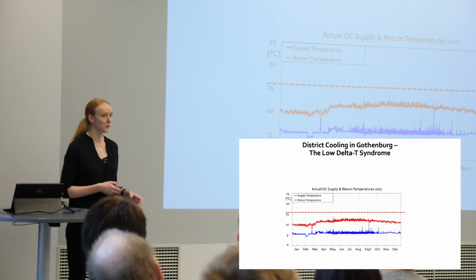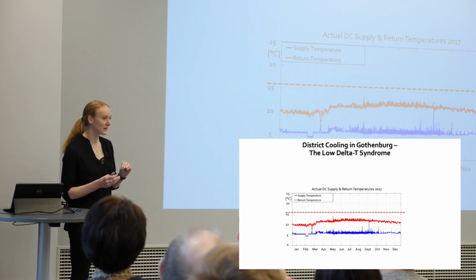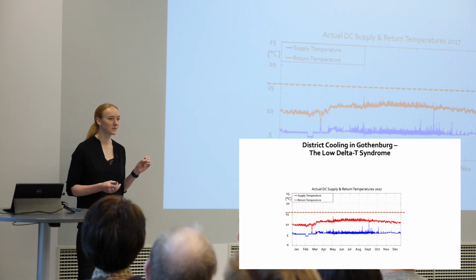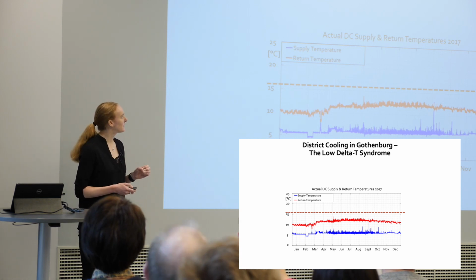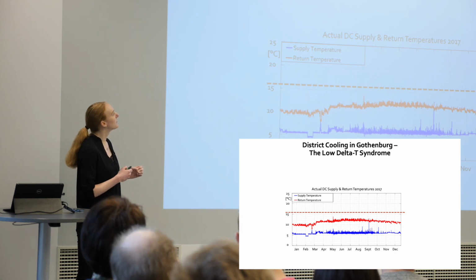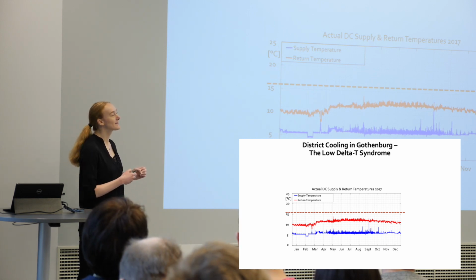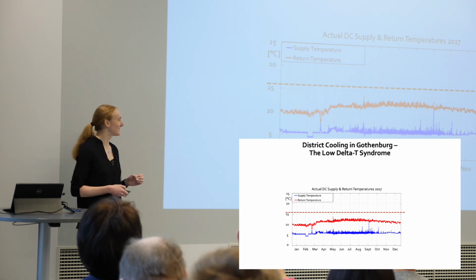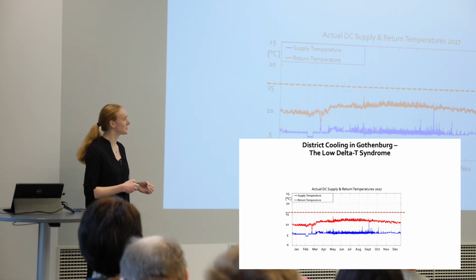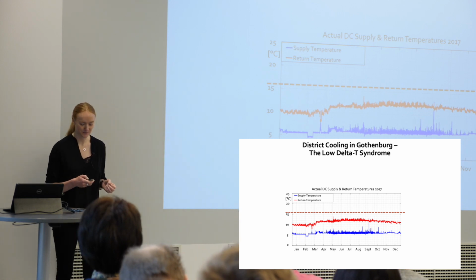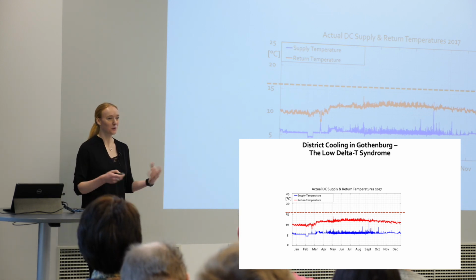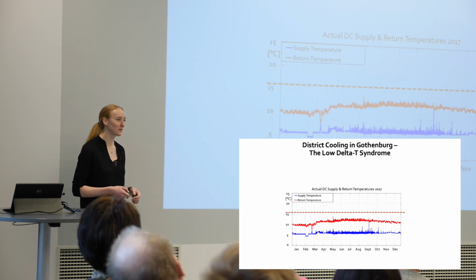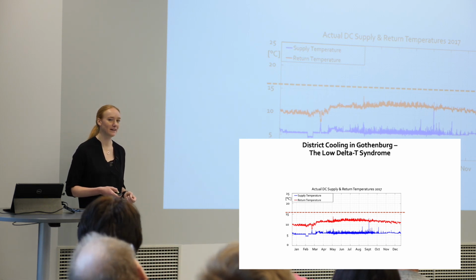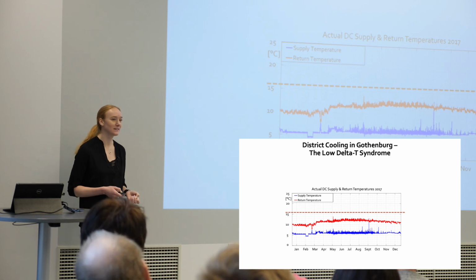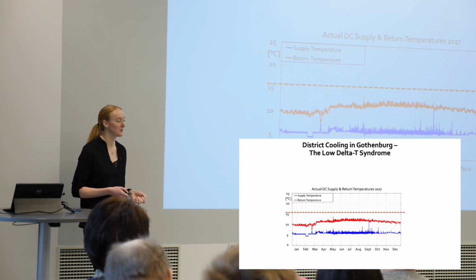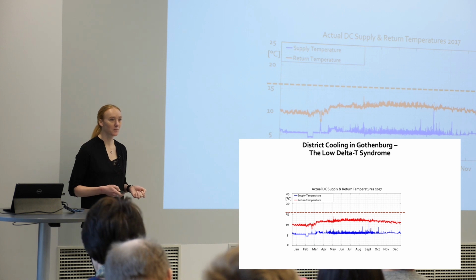These are the temperatures for the large system, so it's not including the smaller system on the north side of the river. But this is the reason why Gothenburg has the low delta T syndrome. The design temperature is essentially never reached in the system. And this leads to more water flow rate having to be pumped in the system. They have to turn on more chillers in order to supply the cooling demand. And it's basically just more expensive and a waste of energy. But it's good because I have something to do.